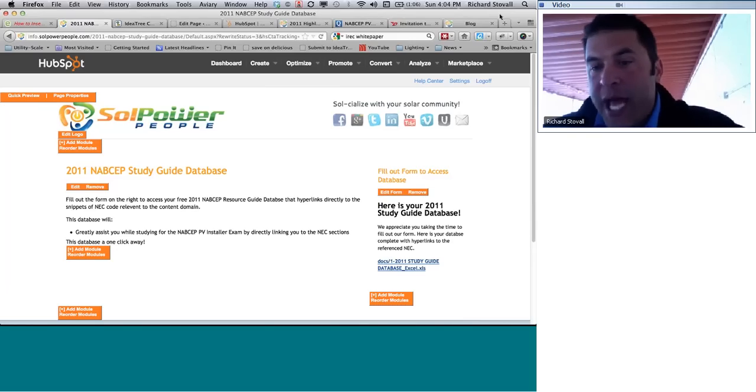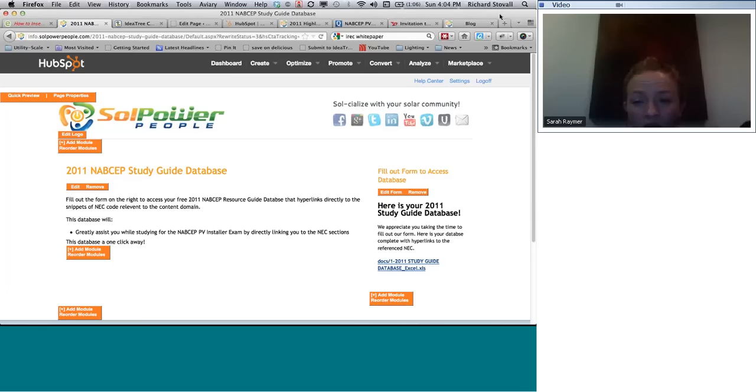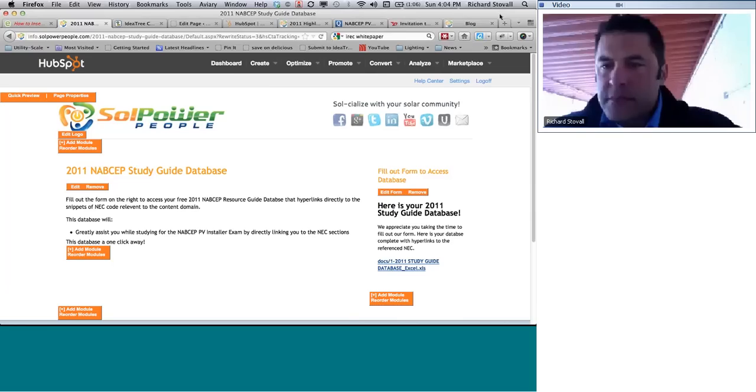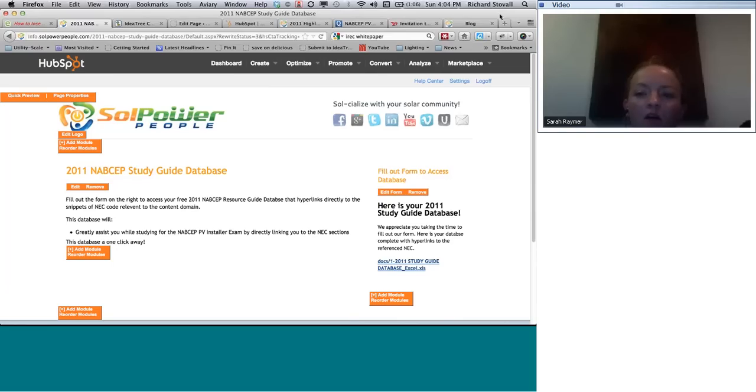But the only way we can do that is by having a lot of eyes going over it. Okay, so the only thing is I either missed a page or I thought that it hadn't changed and it had. But THWN2 is not in the table that is in there. In the current code book, article 310.104, there are a few different types of wires in there, it looks like. So I will change that, but in the meanwhile, you have the NEC 2011 highlighted code. Just know that 310.104A has the specifications for THWN2, which will be a common wire that you'll be using in PV.